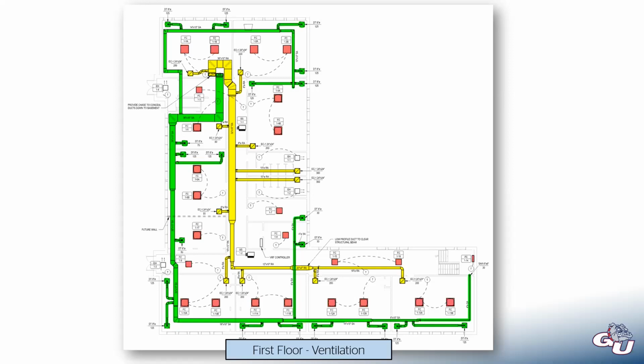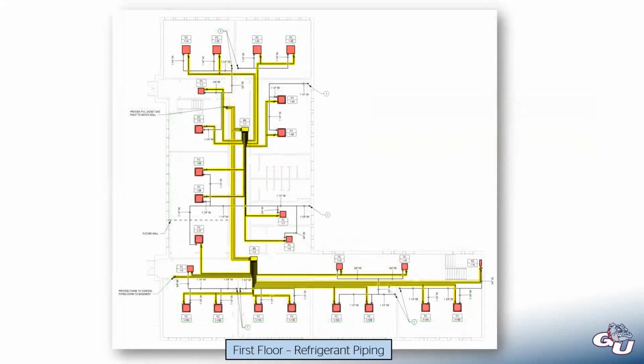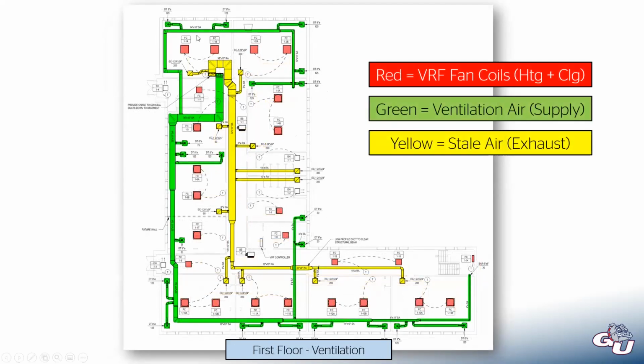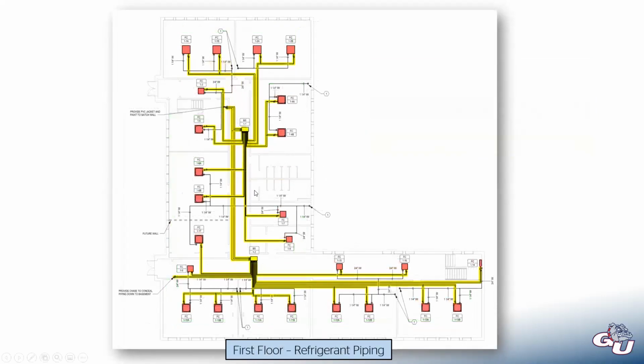The other nice thing about this VRF system is that it lends itself very well to old buildings. I mentioned this is at least a 100-year-old building. Those old buildings are really not designed for modern systems. Normally, we would have ductwork running through this whole building. However, we still have some ductwork. That's how we get our ventilation air through the building. This VRF system with this refrigerant pipe, this pipe is very small, and so it's very easy to run this pipe all over the building, even when you have extremely limited space. Whereas with a more traditional system that requires less refrigerant piping but a lot more ductwork, we would need a lot more space to do that.